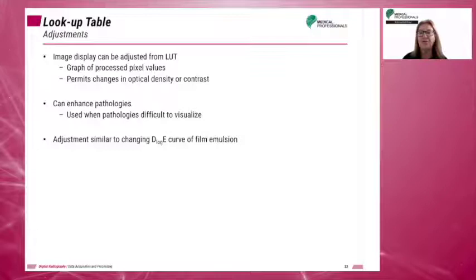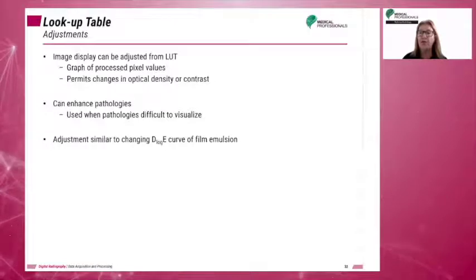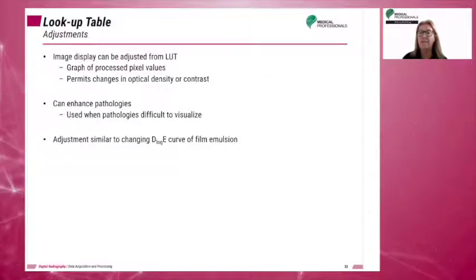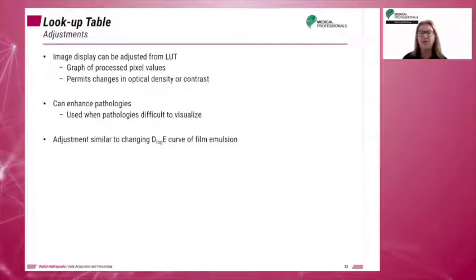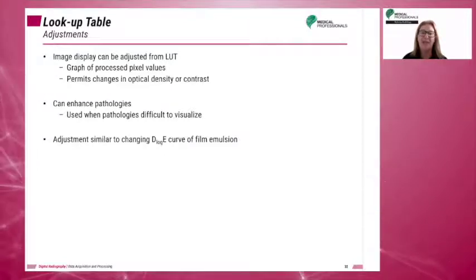In conventional film screen imaging, MAS controlled density and KVP controlled contrast. The film responded in a non-linear way. If MAS was too high or too low, the optical density values would either fall in the shoulder of the H&D curve — too dark — or in the area of the toe — too light — making them indistinguishable from each other. With digital imaging, the response to exposure is linear, so the system is capable of displaying many more shades of gray. The lookup table is also primarily responsible for image contrast as displayed on the monitor.